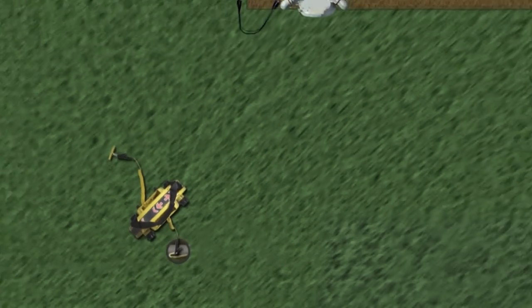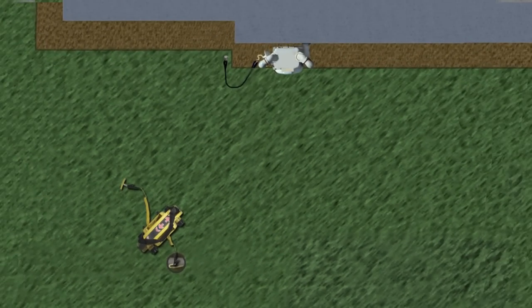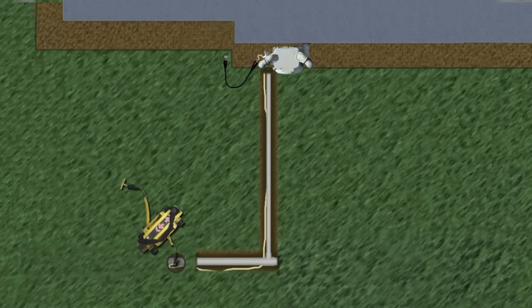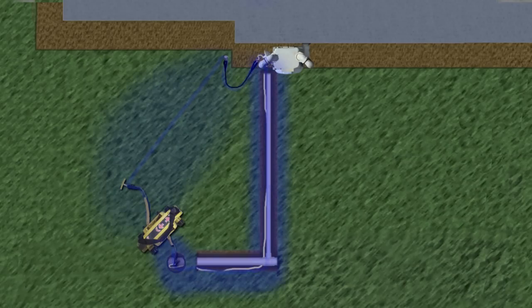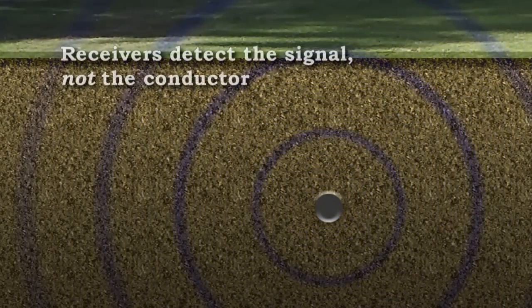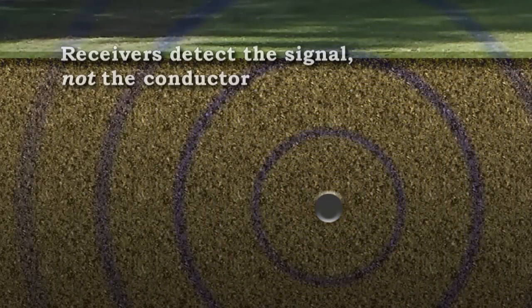Let's start with a look at how the receiver picks up signals from a target utility. In this sample circuit, a transmitter is directly connected to the utility. When the transmitter is activated, it generates an alternating electrical current that flows through the conductor and back to the transmitter through the earth ground. This current flowing through the conductor produces an electromagnetic signal that can be detected by a receiver. When designating a utility's position, it's important to understand that the receiver is actually tracing this signal and not the utility itself. You are assuming that this signal accurately indicates the utility's location below ground.